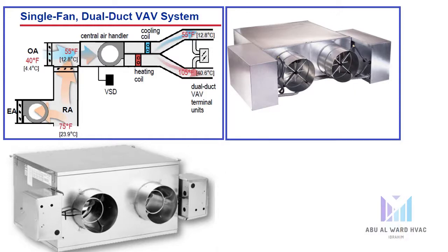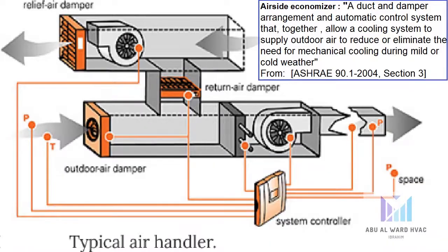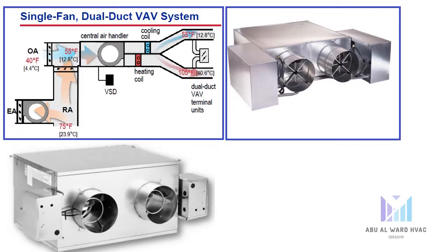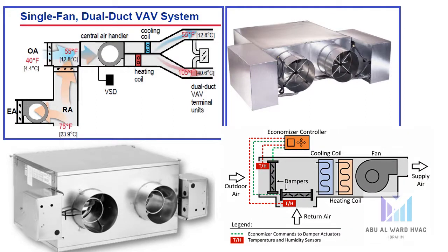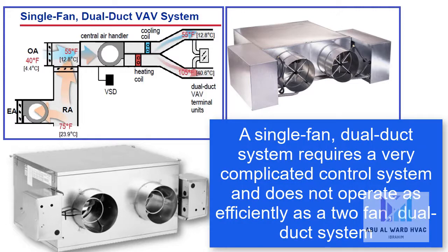In this example, the economizer is controlling the mixed air temperature to 55°F, thus saving energy to operate the cooling coil. However, the heating coil must warm the air from 55°F to 105°F primary air temperature. If the economizer was not activated, the mixed air temperature would be 75°F, requiring less heating energy, but the cooling coil must then operate. Optimizing the energy use of a single fan dual duct system requires a very complicated control system and does not operate as efficiently as a two fan dual duct system.